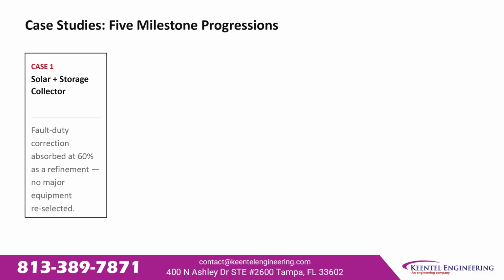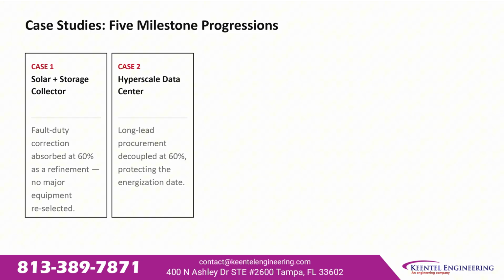The first is a solar plus storage collector substation. A fault duty correction emerged between 30% and 60% because equipment selections had been flagged as preliminary pending system impact study validation. The correction was absorbed at 60% as a refinement. No major reselection required. The second is a hyperscale data center substation where the energization date was the critical constraint. At 60%, the main power transformer was identified as a long lead item and procurement was decoupled from the remaining design work protecting the schedule.